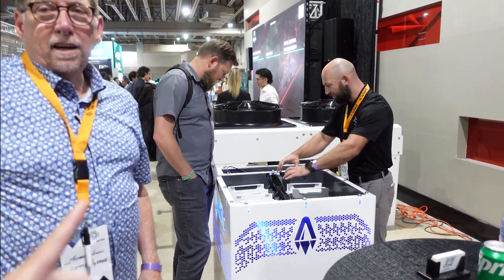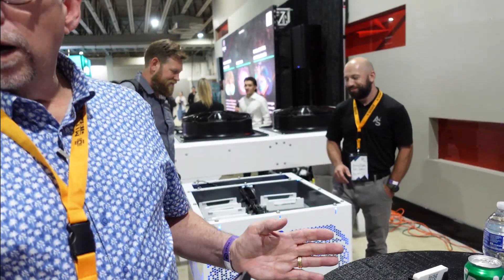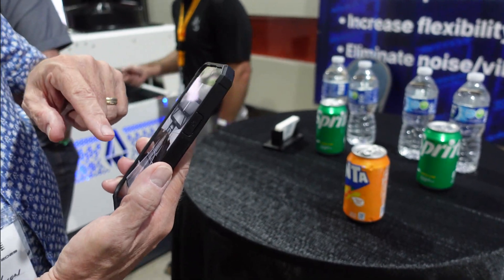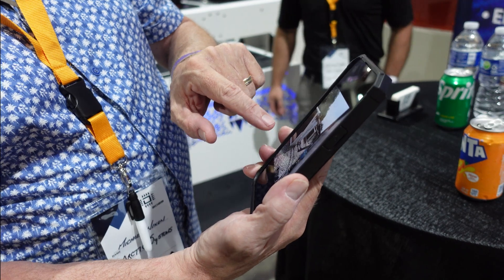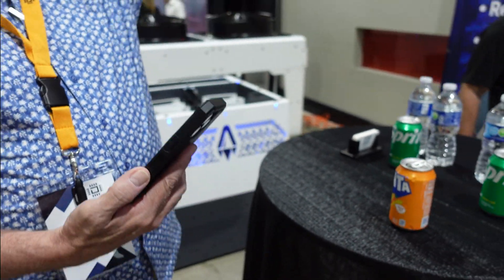The container we saw pictured was one megawatt — that's correct. What's the biggest you guys have done? Our systems are modular, so you can scale depending on the job. Here's one where the modules are all put together — this is six megawatts all connected. Outside you can see all the dry coolers along the side, but we found they actually perform better on top because you don't get leaves and dirt pulled in, and you get better cooling up where the air stream is.